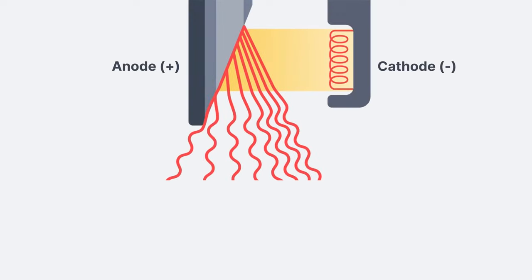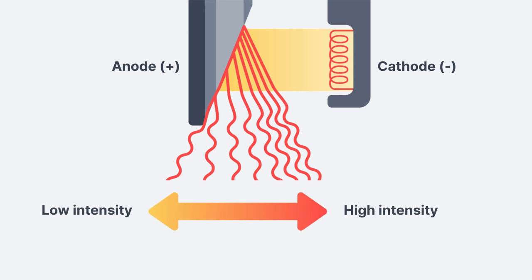Unfortunately, the angled anode does have one negative consequence. The angle of the anode causes a variation of the beam's intensity across the x-ray field. Specifically, there are fewer x-ray photons on the anode side of the beam compared to the cathode side. So we would say that the cathode side has higher intensity and the anode side has the lower intensity.